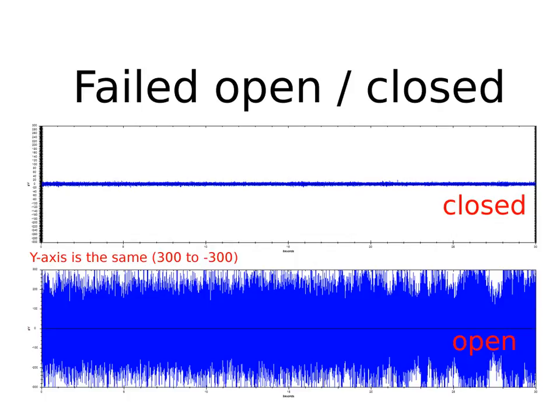A dynamic signal of a steam trap that has failed closed shows very little signal and a cold temperature, indicating the trap has failed closed or there's a blockage somewhere. Compare that with a trap that's failed open — it looks similar, just a sea of noise, but the y-axis shows much higher signal, indicating the trap is wide open with a lot of turbulent flow across the valve.